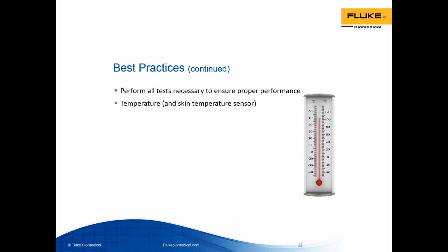So another very obvious best practice is to perform all the tests that are necessary to ensure the proper performance, right? So there's a complete list of tests and criteria that can be found in the IEC 60601-2-19 standard or the manufacturer's service manual. But here are the basics. So for temperature, we need to make sure that the incubator warms up in the time specified in the manufacturer's manual. We've got to make sure that the overshoot temperature doesn't exceed 2 degrees Celsius above that set point. Check all the surfaces that touch the infant, from the mattress to anything left inside, and make sure that they don't get too hot. So test to determine when the incubator's temperature stabilizes and then stays at that temperature setting for at least an hour, so STC. And then finally, verify the temperature is uniform and the same throughout the compartment.